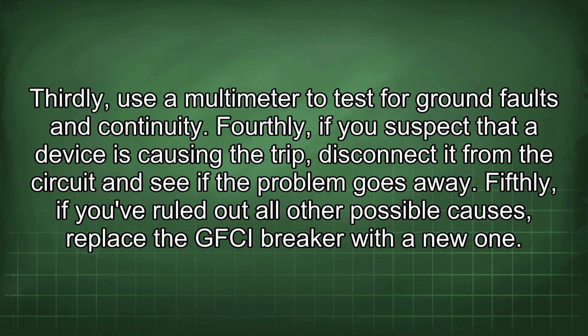Fourthly, if you suspect that a device is causing the trip, disconnect it from the circuit and see if the problem goes away. Fifthly, if you've ruled out all other possible causes, replace the GFCI breaker with a new one.